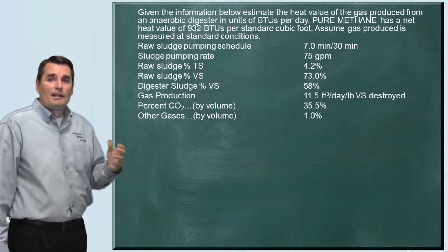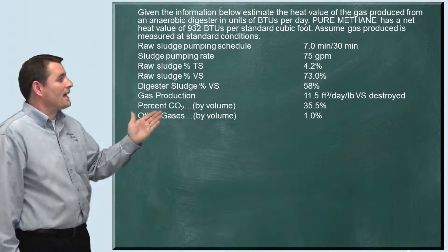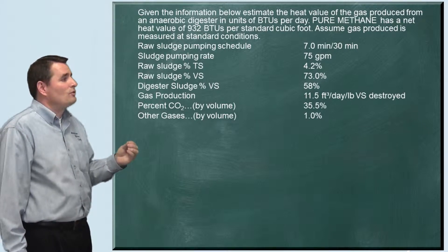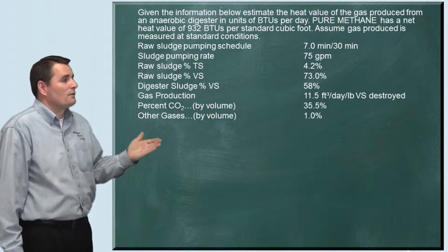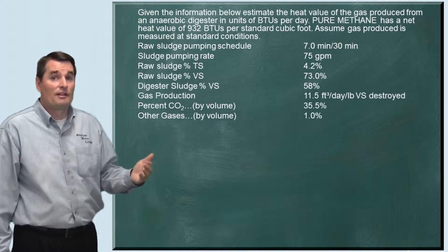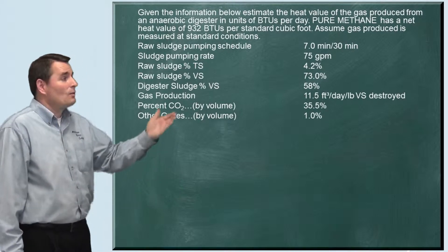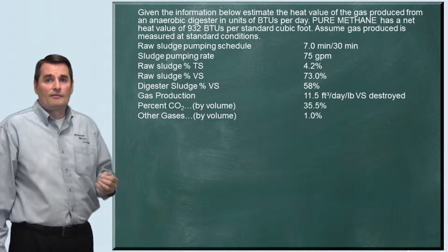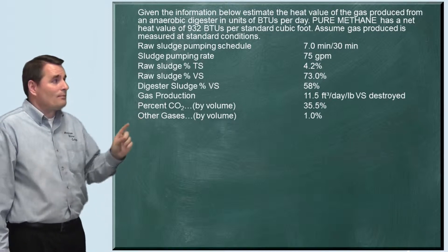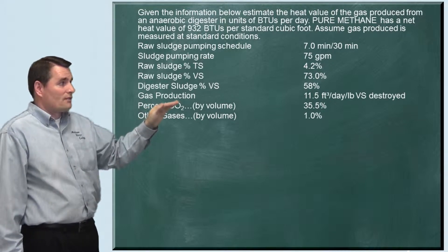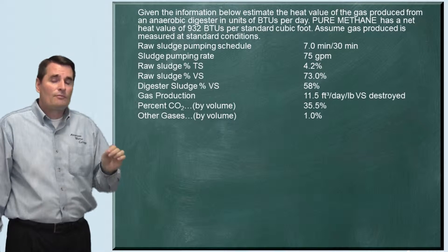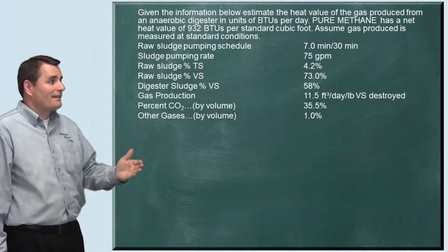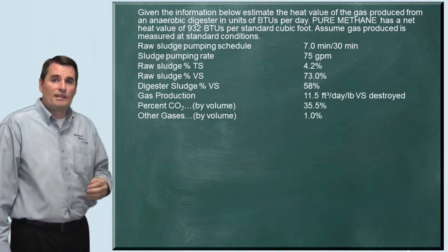The digested sludge percent volatile solids is 58% — that's after reduction in the digester. They also gave us an equivalent for gas production: for every pound of volatile solids destroyed in the digester, we get 11.5 cubic feet of gas produced. So for every pound per day of volatile solids destroyed, we get 11.5 cubic feet of gas.